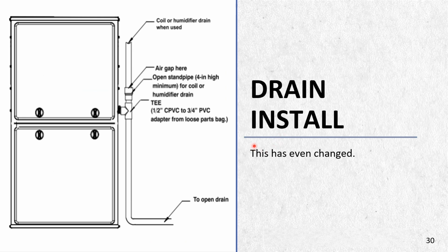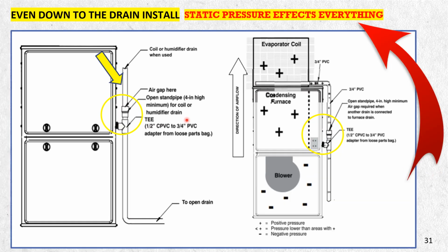Everything, like I said, has even changed. Even the drain has changed, and how you are to run your drain lines has changed due to static pressure. If you look at this, this is the proper way, because here, a blower motor, your return air is a negative. So you're pushing air up into a condensing furnace. Let's say it's a 92 or higher condensing furnace up into a coil.